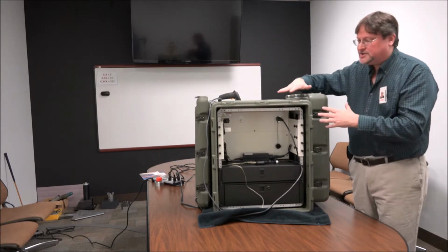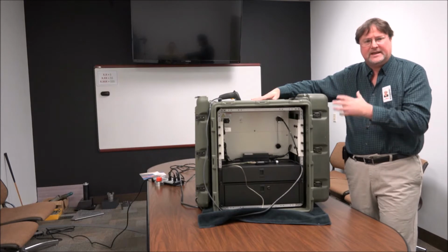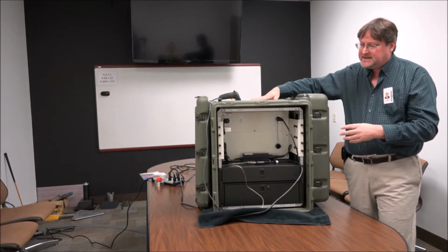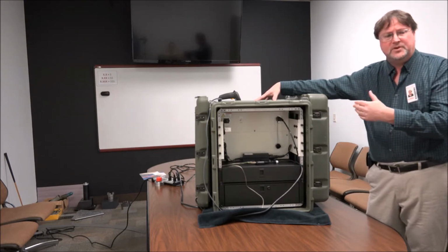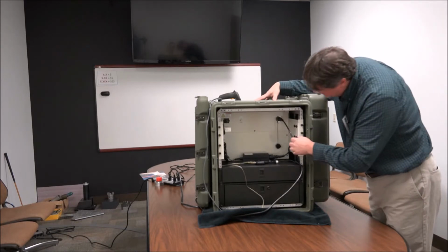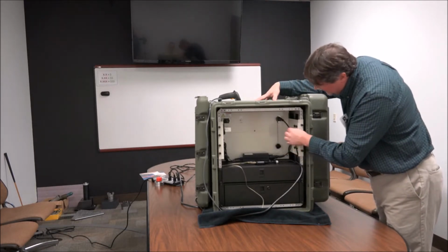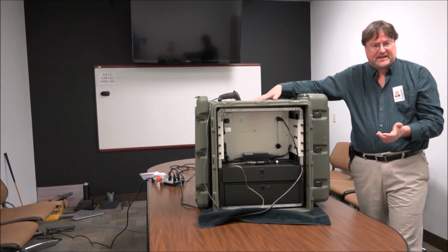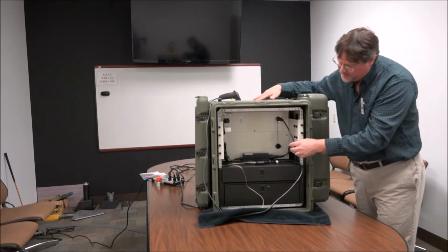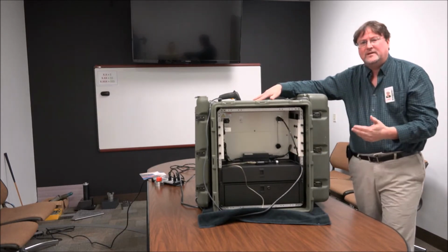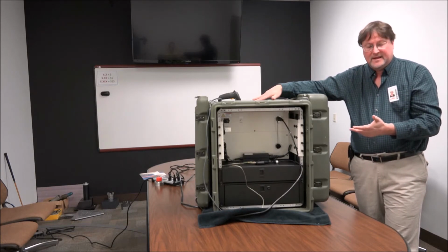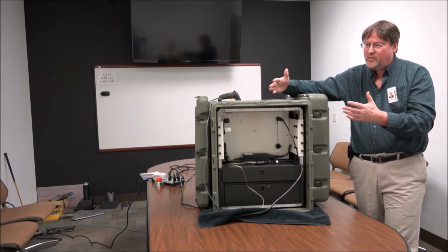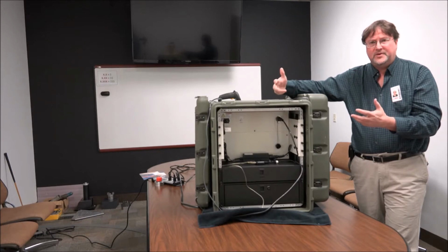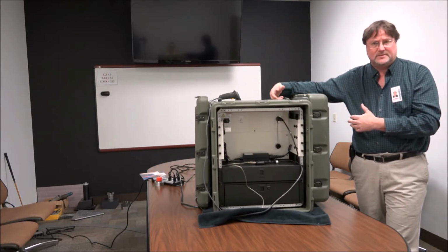We also want to control any other power sources that might come into the system. So to protect against a computer failure or a computer source of power, we connect between the computer and the unit through a fiber optic connection. This is a military-grade IP65 washdown fiber optic cable that, when connected, there's no way that electrical power from the computer can get to the tester.